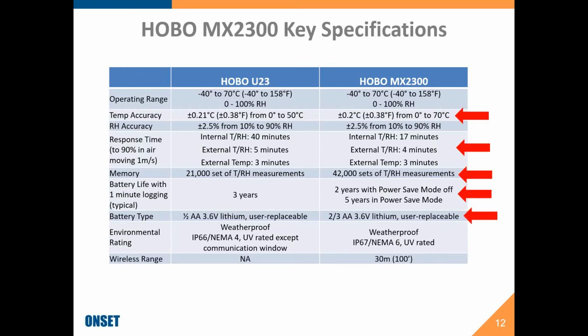We do have a slightly larger battery in here than the U23s. It's a 2/3 AA lithium battery, and because of the wireless communications, that required going to a slightly larger battery to get those battery lives expressed above.